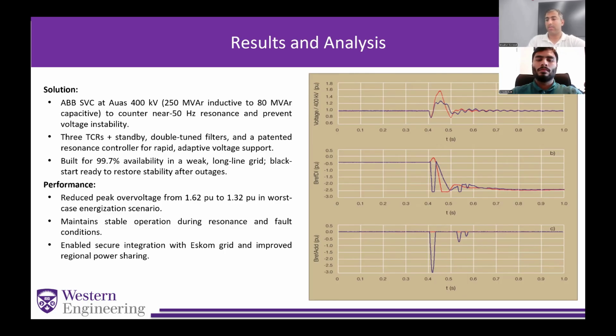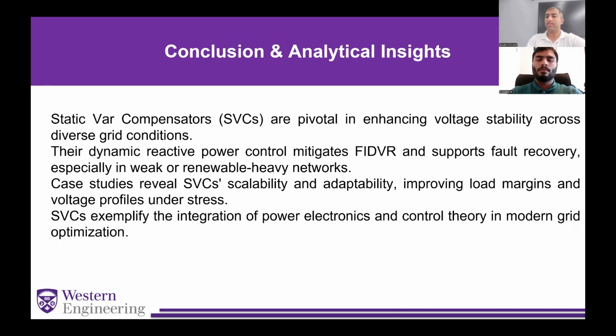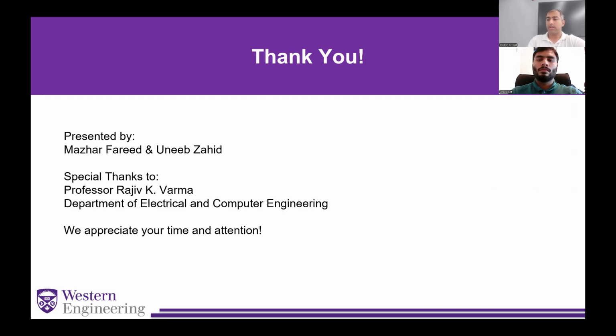So moving on to the next slide, that would be about conclusion and analytical insights. According to our whole study across wildly different grids, SVCs did the same essential job, delivering precisely timed VARs that keep voltage where the system can breathe. They mitigated FIDVR, expanded load margins, filtered harmonics, and neutralized resonance, what they are supposed to do, using the same toolkit tuned to local realities. If you remember one thing, let it be this: fast, intelligent reactive power is not optional in modern networks, it's the backbone of stability. And thank you for your attention and curiosity.